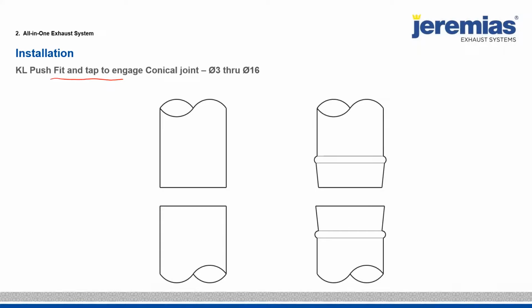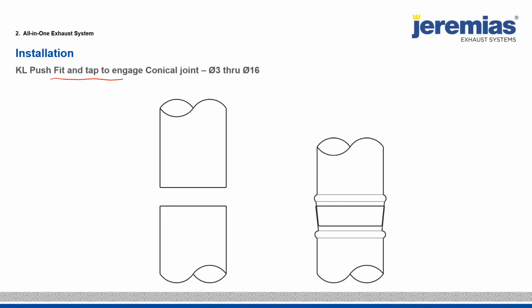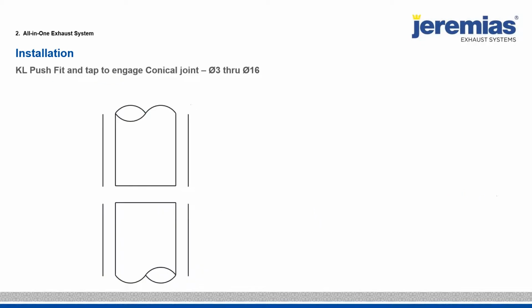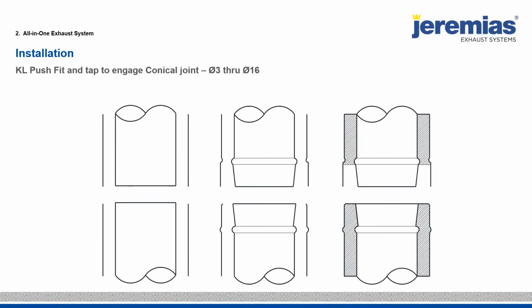You form the conical, which this illustration is exaggerated. You simply push the two pieces of pipe together, and then they're pushed or tapped into place, and that forms the connection. There's no gasket, no lubricant, and that's what we have, the 90 inches of water column of pressure rating. On the double wall system, we actually shove insulation between the walls, and that insulation is what holds the inner and outer pipe together. We actually wire cut this mineral fiber, or we compress the ceramic fiber to make sure it's holding the inner outer pipe together. So these are actually floating inner and outer pipes.